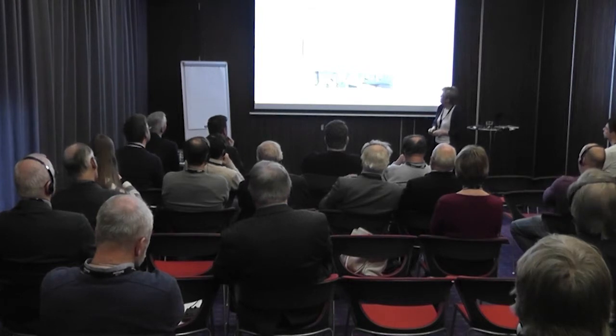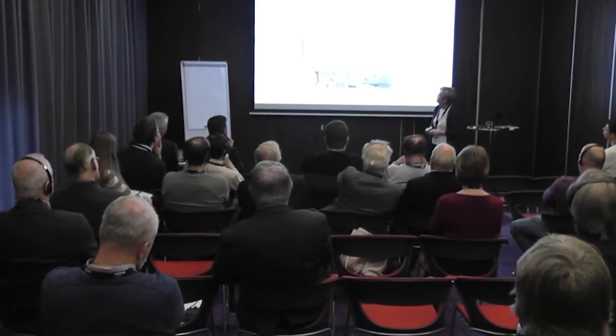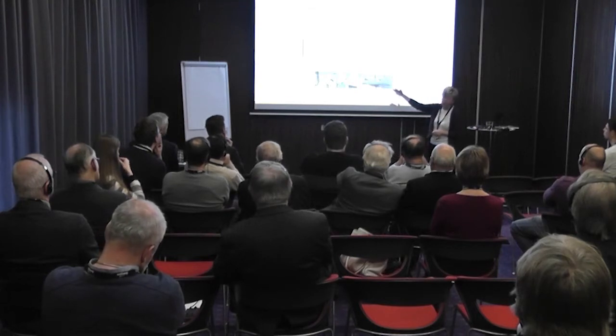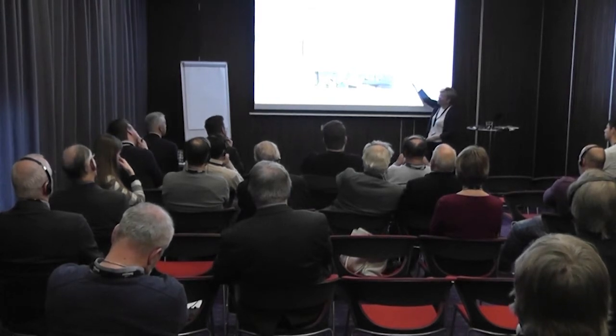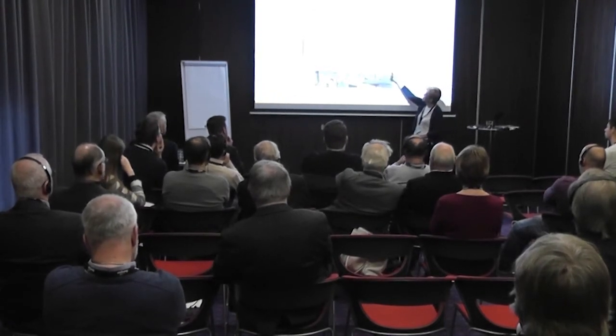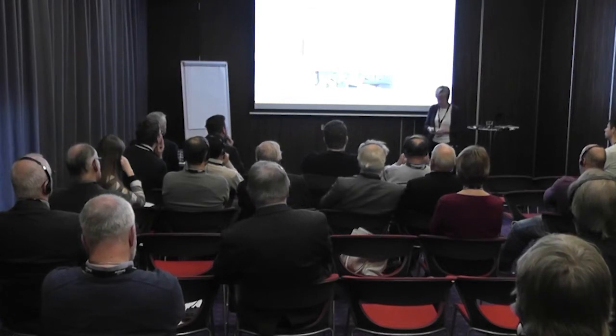So they made studies of the fume hoods, investigating how they were used and how many hours they were used by the laboratory people. We made queries to the people who were going to move into these buildings. And as you see, it's very important that they are structured and close their fume hoods when they don't use them, because when it's closed, the exhaust air is 200, but while it's open, it might be up to 1200. So the use of fume hoods is very critical.